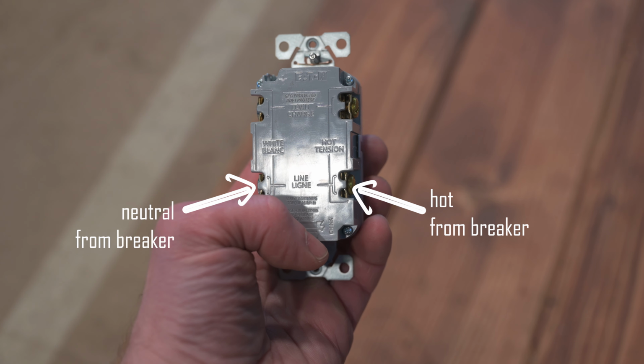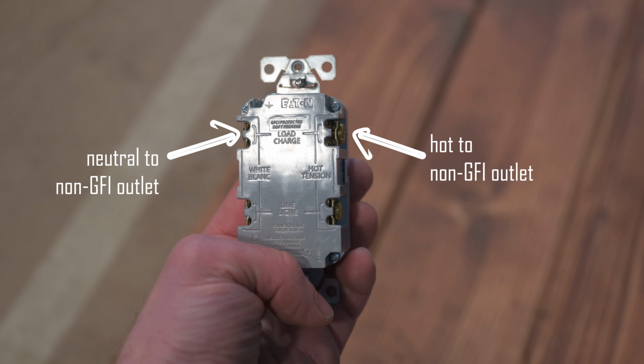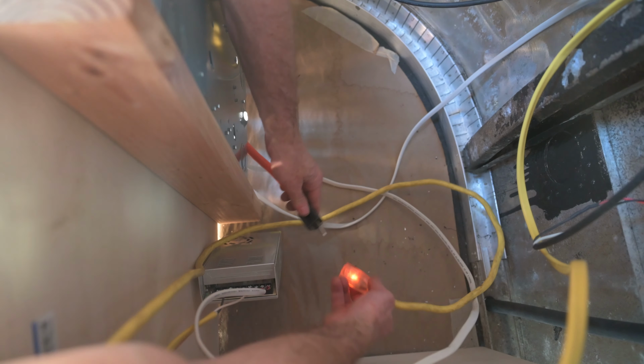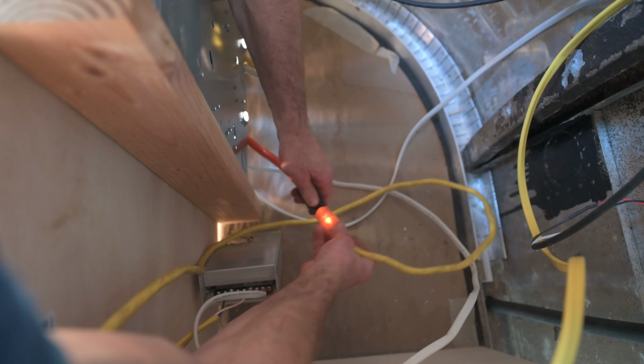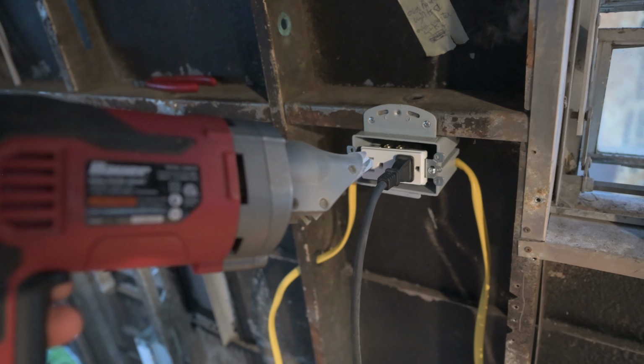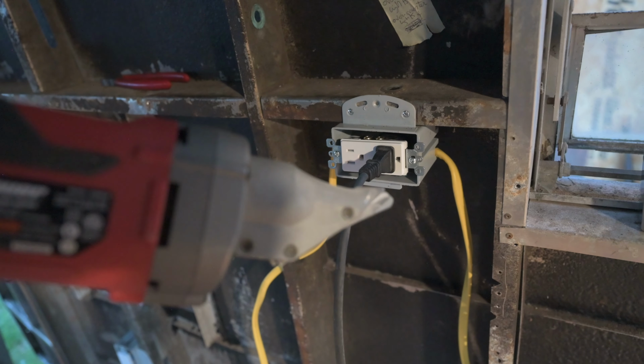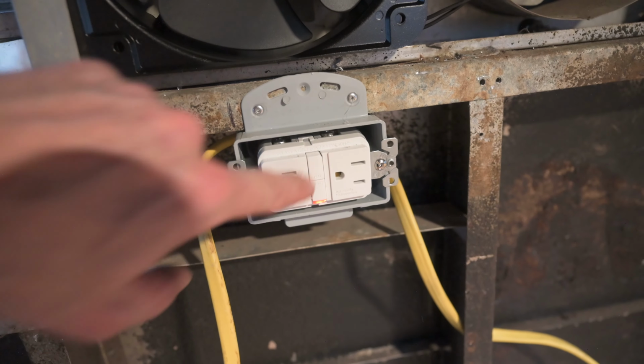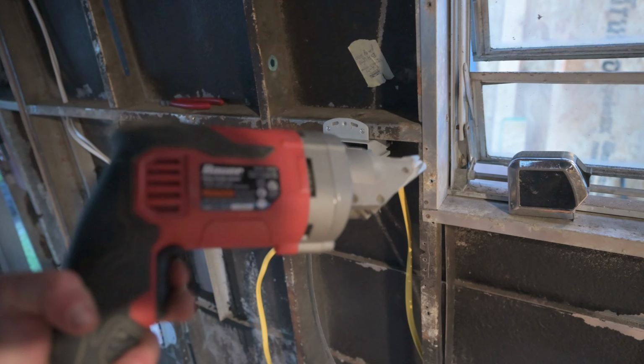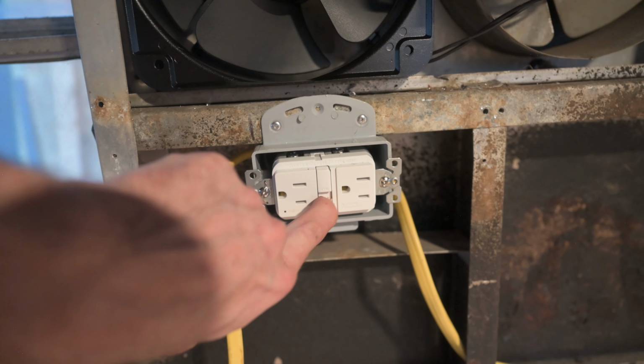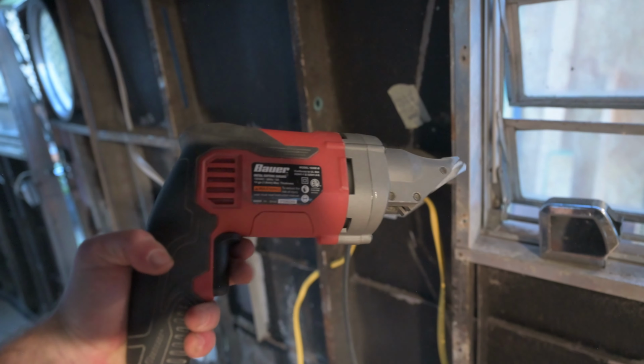The hot and neutral wires from the breaker panel connect to these terminals, while any other outlets you want protected are wired to the load terminals. Attach the ground wire, and that's it. To test it, plug in the trailer, close or turn on the breaker for the circuit, test your plug-in power tool of choice, and see that it runs. Press the test button, see that the tool no longer runs, press the reset button, and see that the tool once again runs. You can repeat this test for any other outlets connected to this GFI outlet.